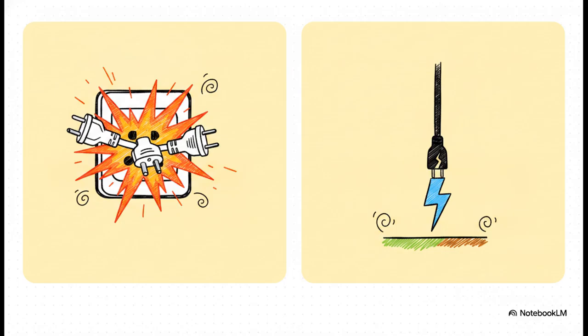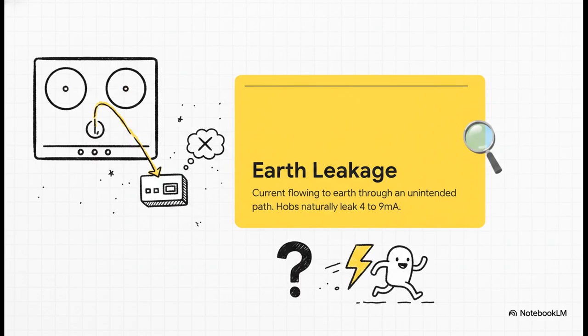But then you've got an RCD, or residual current device, which functions just like the GFCI we just mentioned. This protects against earth leakage. It triggers in absolute milliseconds if it senses even a tiny amount of current escaping to the earth, because that usually means a human is getting shocked. And that brings us to earth leakage. That is exactly what the GFCI is hunting for. But here is the massive plot twist. Modern induction hobs actually produce a tiny, totally harmless amount of earth leakage just as a normal byproduct of their high-frequency electronics. We're talking usually between 4 and 9 milliamps. They literally leak by design.